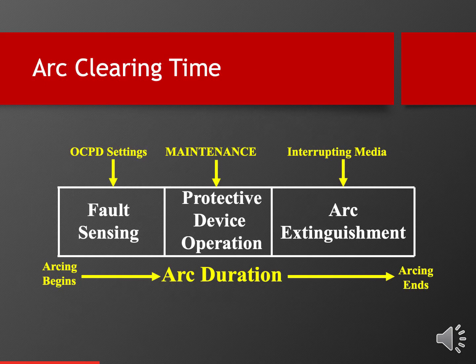Now what you see here is the three components of what we call arc clearing time. And in the simplest terms, arc clearing time means it's the duration in time, in seconds, from when the arcing event starts to when the arc is extinguished. There's three components to that, and you can impact two of the three. The first one is the fault sensing. How long does it take for the overcurrent devices to recognize that the current flowing in the system is in fact not okay?